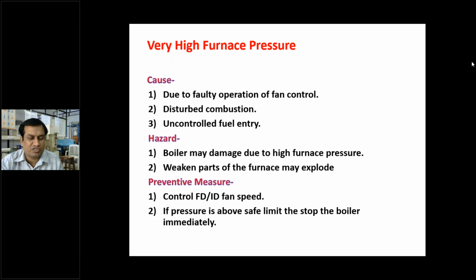So due to high pressure, some of the parts may become weakened, and those weakened parts may convert into an explosion. How to prevent this very high furnace pressure? You have to control these fans, that is the FD fan and ID fan speed. So this forced draft and induced draft fan should be controlled.